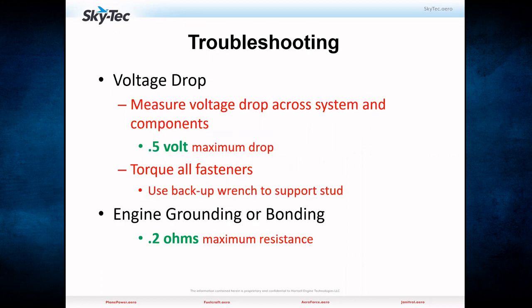More on troubleshooting: voltage drop, 0.5 volts drop, give you something to aim for. If you go from the battery, you've got 12 volts on the battery. You check the input to the contactor, you've got 11 or 12 volts there, and at the output of the contactor you have 10 volts — you've dropped 2 volts inside that contactor. You've got too much resistance in that contactor, creating too much drop. It's not going to work — change the contactor.